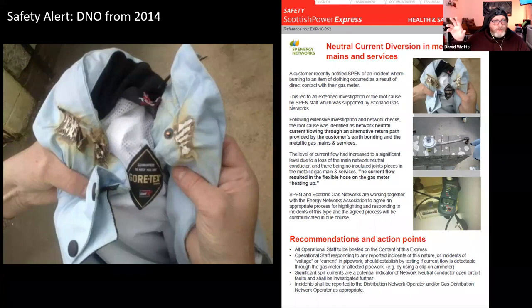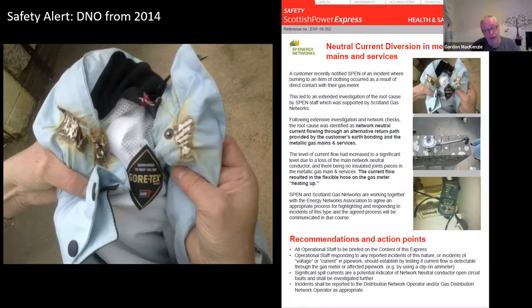And was that the demand of the neighbouring property? It turned out it was quite significantly more than that. It was quite a few properties. And the reason we found that out was almost by chance. We had isolated a section of the network. We had removed all the cut-out fuses in the property. We had cut the phases L1, L2, L3, and the boys were about to cut the neutral when the hairs on the back of their neck stood up, and they thought, can we do this safely? At that point, we put the clip-on ammeter around the neutral, even though the radial section of the cable was completely isolated. It turned out half the housing scheme was using that as the route. So had the boys cut that, we would have lost the only neutral back, and we would have had the expectation of an open circuit neutral at that point with all the damage.